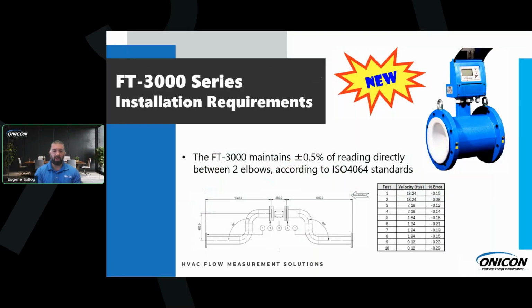So talking about straight run requirements, this is our new certification. Nothing was changed on the meter. It always performed this way, but we actually sent it out and got it certified according to ISO 4064 standards to be better than plus or minus 0.5% of reading accuracy between two elbows. So 0 straight run, 2 elbows, and you can see the test results there in that table. It looks like the worst that we were was negative 0.29% error at just over 1/10 of a foot per second.